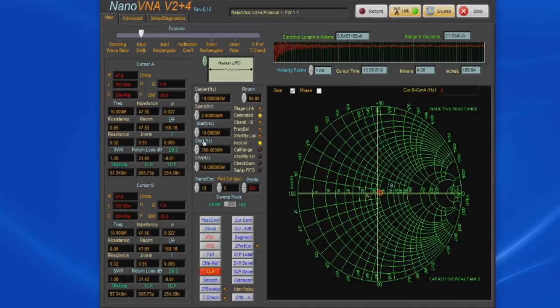If we go out of range, so for example, let's go to 301 megahertz, you can see now this calibration range error comes on. Again, we can go back within range and everything's going to be fine. So all the frequencies are in hertz. So M means meg, small k would be kilo.